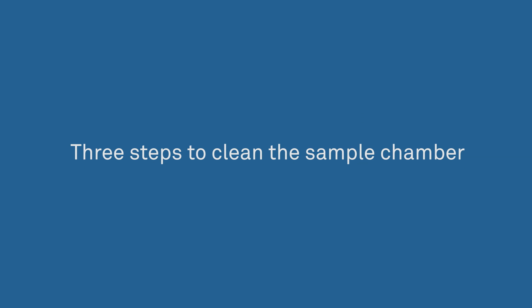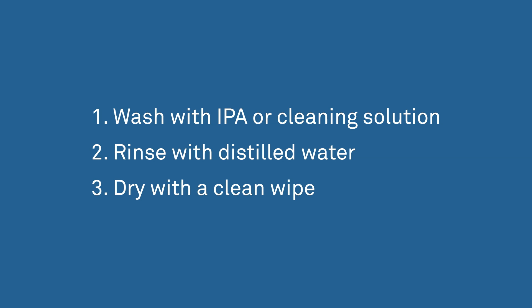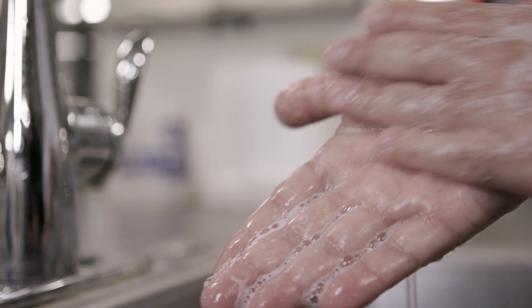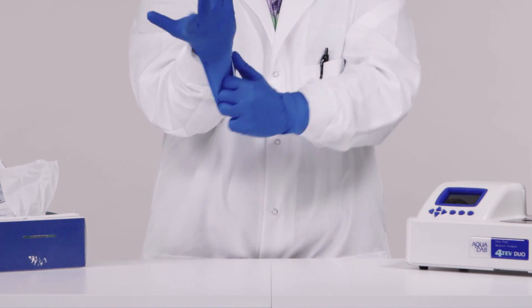There are three steps to cleaning the sample chamber surface area and sensors. 1. Wash with isopropyl alcohol or cleaning solution. 2. Rinse with distilled water. 3. Dry with a clean wipe. To start, turn off power to your instrument and unplug the power cord. Wash your hands thoroughly or wear lab gloves so dirt and natural oils on your hands don't contaminate the cleaning materials or the sensors.